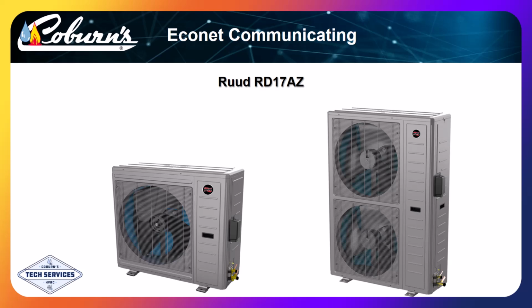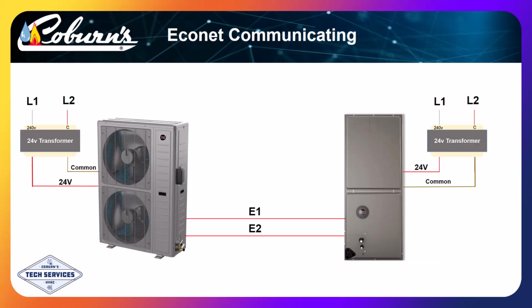If it's connected to a matched Ruud communicating Econet system, there is now a transformer in the outside unit and the inside unit. Both transformers are used to power control boards that provide communication on the Econet system. Only 2 wires need to be ran between communicating equipment when using an RD17. The transformers on both pieces of equipment need to be identically connected to the same phases of main power, like shown here.